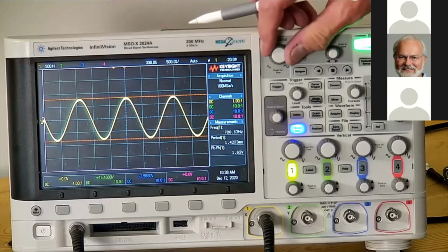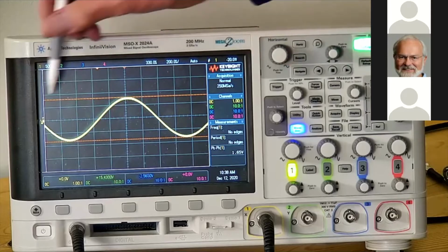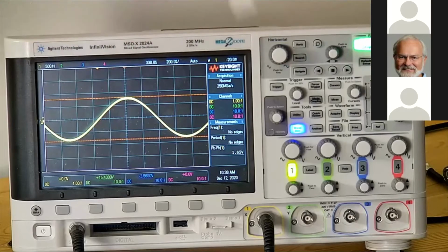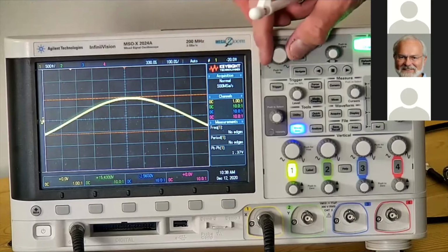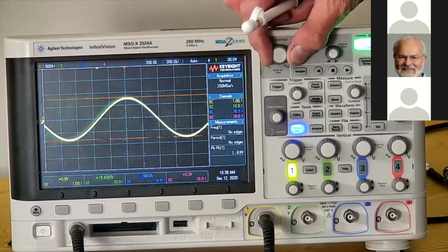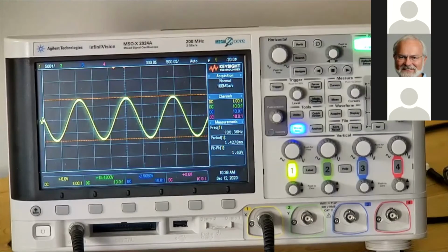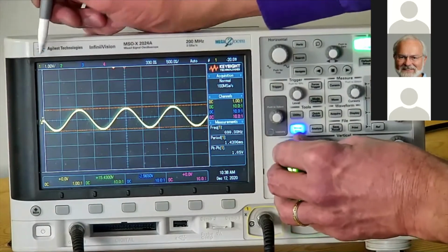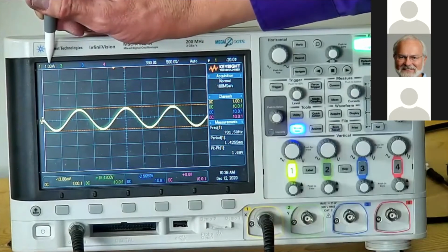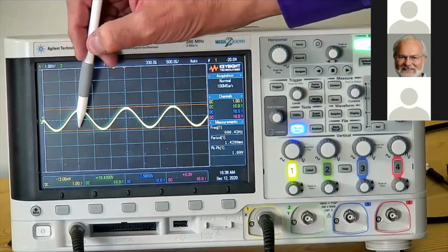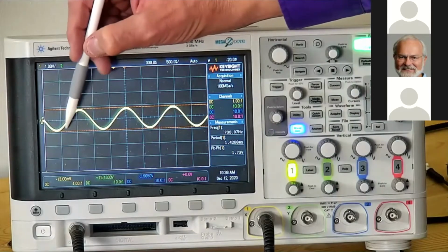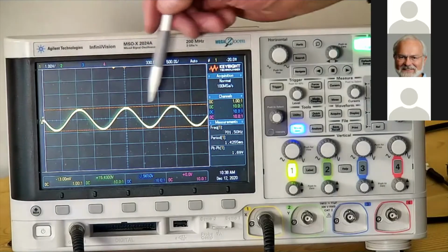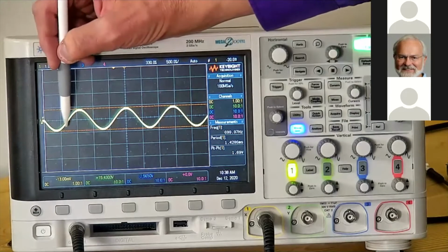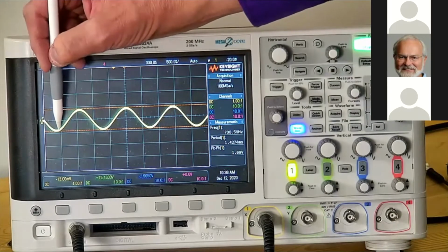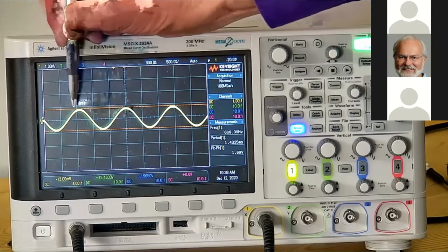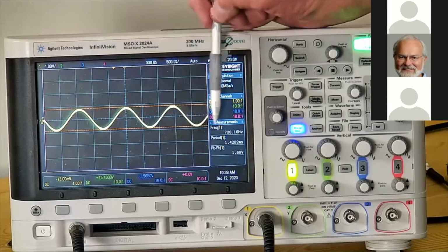If we turn that down to 200 microseconds per division, now you can see the waveform is spread out a little bit because the amount of time is less per division. And then the voltage right here is now set at 1 volt per division. So we're looking at a little less than 2 volts from peak to peak there. Now the scope looks at all these samples, computes and finds the low point and the high point, and puts these markers up here. And it's telling us that peak-to-peak voltage is 1.6.